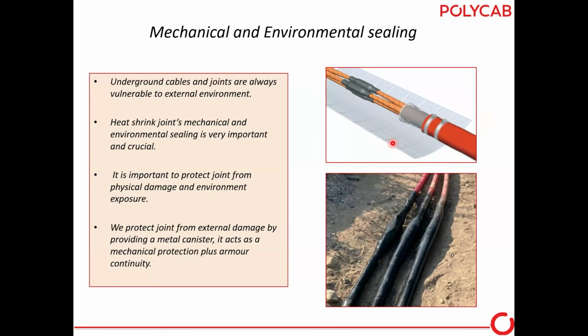Over that we provide the outer sleeves. That is basically exactly like the cable outer sleeves, which we shrink. From here, water will not go inside, the outer sleeve being such that water or moisture should not get in from this point. If it goes inside the joint, then the joint will definitely fail today or tomorrow. So the strongest point, actually, in any joint and termination is that water should not go in.